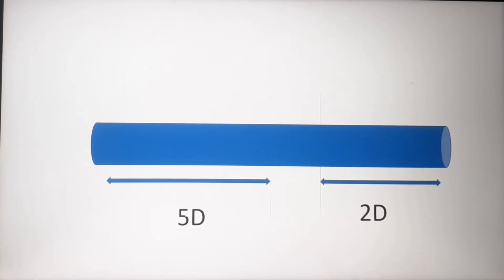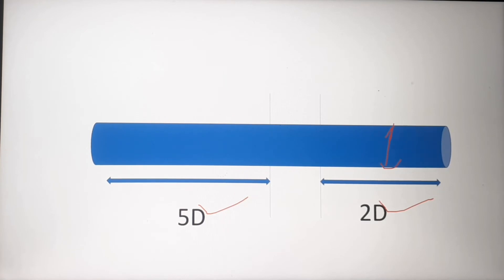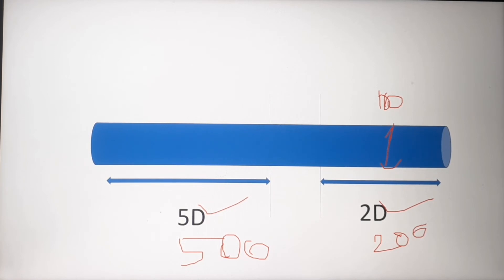That is why people follow the 5D-2D concept. Even if there is a bend, you have to offset the PT meter from the bend or T. Here, D is the diameter of the pipe. For example, if D is 100 mm, then 5D is 500 mm and 2D is 200 mm. So you multiply D by 5 or 2 accordingly.